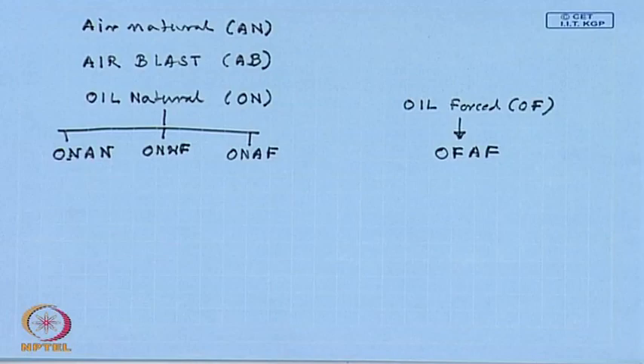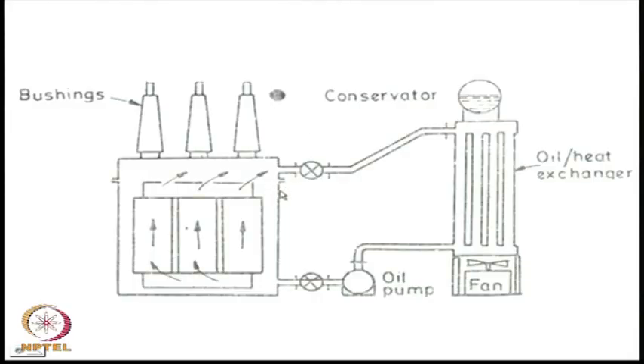Such a scheme is shown in this diagram. It is interesting to note that this scheme can operate in variable mode. For example, the oil pump and the fan need not be on all the time. If the transformer is lightly loaded and dissipating less heat, then both the oil pump and the fan may be turned off, and the scheme can work in an oil natural air natural cooling method. If the load increases to some more extent, then maybe the fan will be turned on first, so that it will work as an oil natural air forced method. It is only at near about rated load or at rated load that it will work as an oil forced air forced cooling method. This way the power consumption for cooling will come down and the overall efficiency of the transformer will increase.